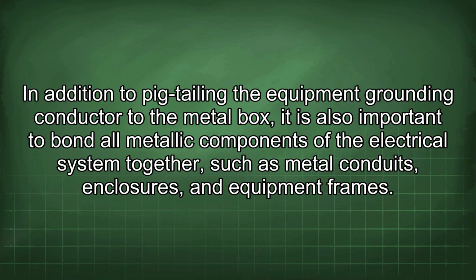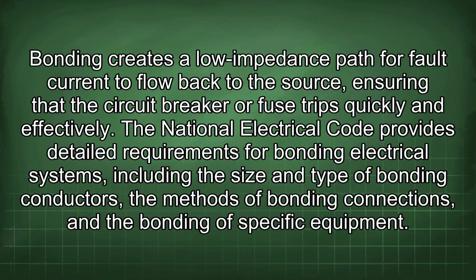In addition to pigtailing the equipment grounding conductor to the metal box, it is also important to bond all metallic components of the electrical system together, such as metal conduits, enclosures, and equipment frames. Bonding creates a low impedance path for fault current to flow back to the source, ensuring that the circuit breaker or fuse trips quickly and effectively.